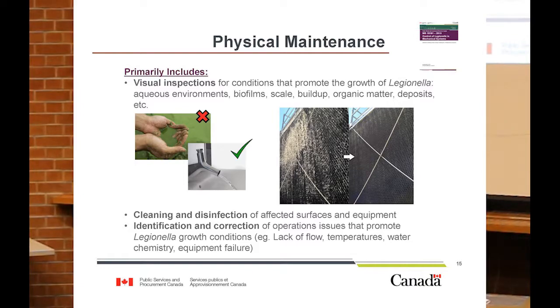And then the physical maintenance that we're looking at doing primarily is regular visual inspections of equipment for conditions that could promote the growth of Legionella. So looking for biofilms, scale, buildup, organic matter, any deposits. And then making sure that we clean those systems or disinfect them if any of those conditions are present, as well as trying to identify and correct any operational issues that could promote the growth. So lack of flow conditions, could be a valve that's seized, could be a pump that's turned off or failed, could be a chemical dosing pump that's failed. So it's identifying those issues as quickly as possible and correcting them.